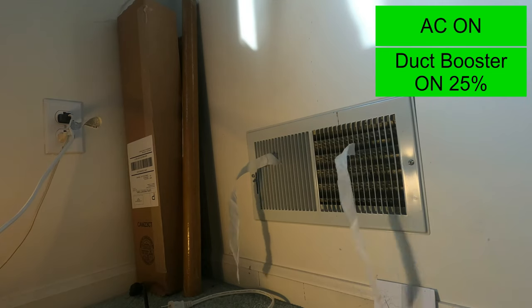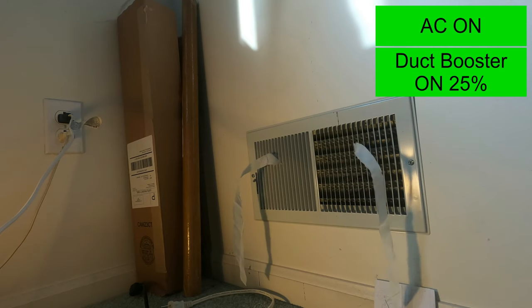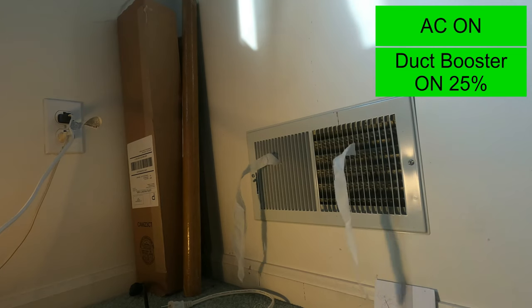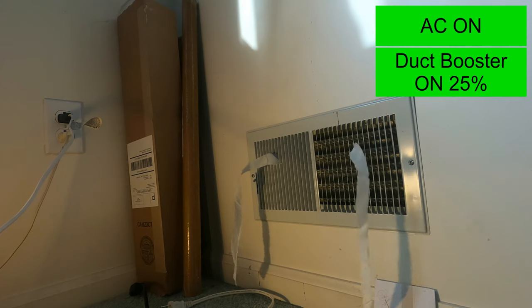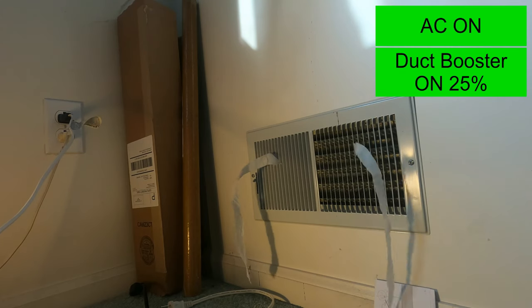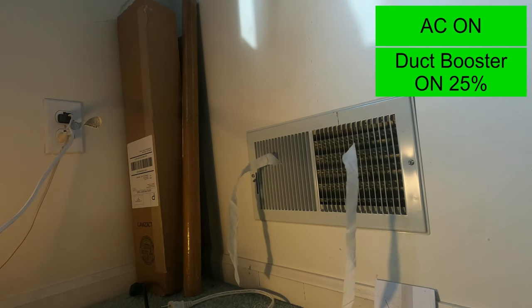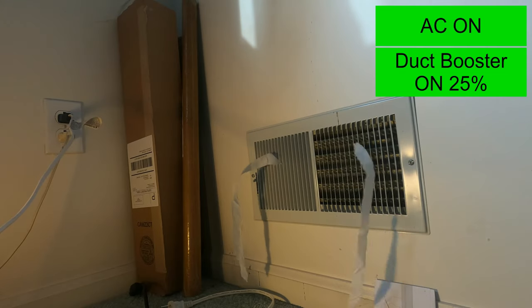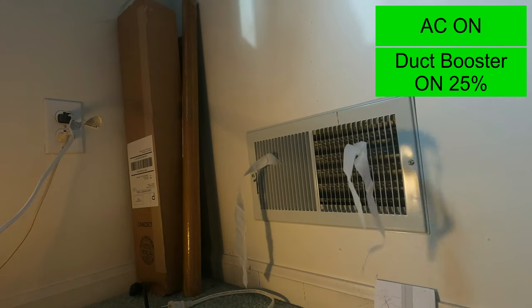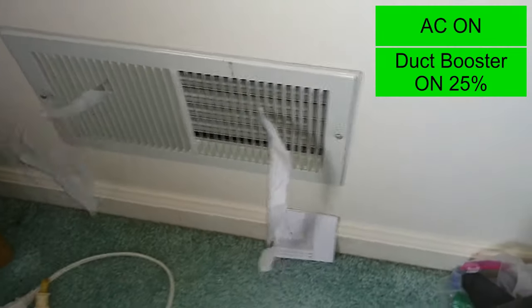Adding the booster created airflow balance in the system, by providing the faulty duct with the corrected airflow allotment the system was designed to provide. Rather than pirating air, I say it's Robin Hooding air. It draws no more air from the system than would have been delivered had the original installation been done correctly in the first place.